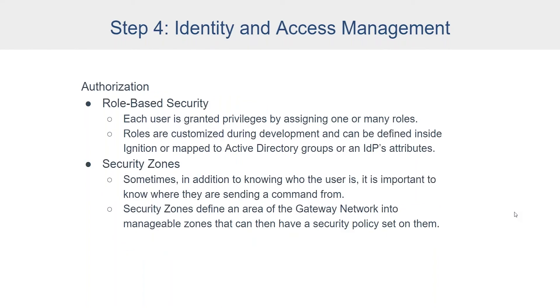Now that you're logged in and authenticated, it's time for authorization. Each user is granted privileges through the assignment of roles or security levels. Roles are customized during development and can be defined inside Ignition or mapped to Active Directory groups or an IDP's attributes. In addition to knowing who the user is, it's important to know where they're sending a command from. Security zones define areas of the network into manageable zones with a security policy. A user logging in right next to a piece of equipment may have read-write control, but if they log in from their desk at a different IP address, they get a different level of access — even if it's the same user with the same roles.